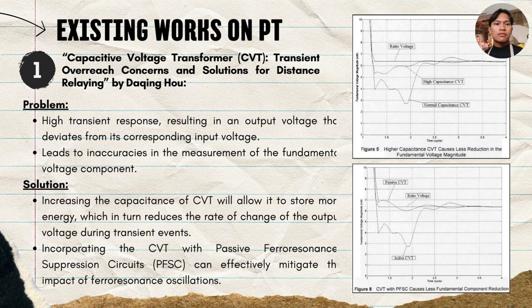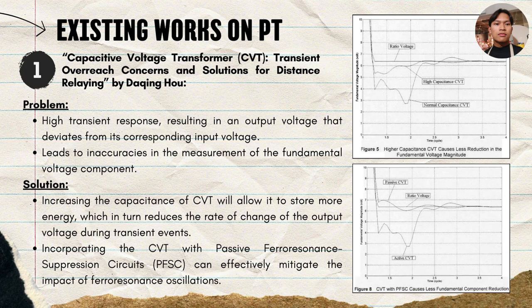Looking at existing works on potential transformers, the first research paper is about capacitive voltage transformers (CVT). The problem discussed is the high transient response which results in output voltage deviating from the input voltage. The solutions proposed are: first, increasing the capacitance of the CVT to store more energy and reduce the rate of change of output voltage during transient events — as shown in the first graph, the CVT with high capacitance has a lower transient response. Second, incorporating the CVT with passive ferro-resonance suppression circuits, which can effectively mitigate the impact of ferro-resonance oscillations — as seen in the second graph, the CVT using the passive circuit has a lower transient response compared to one using an active circuit.